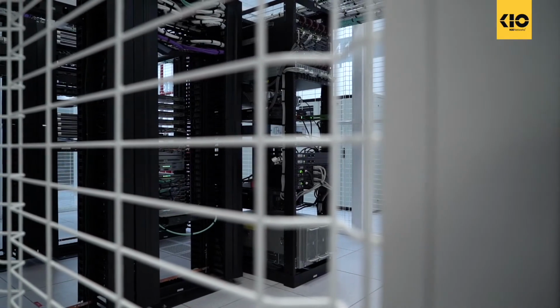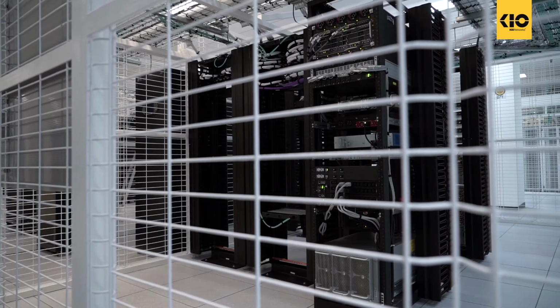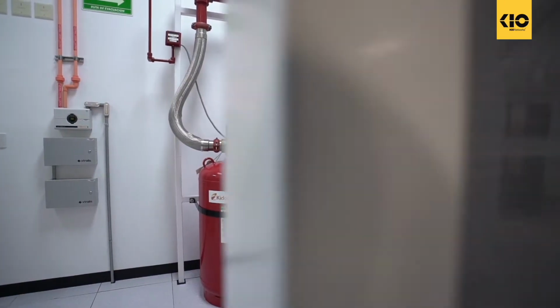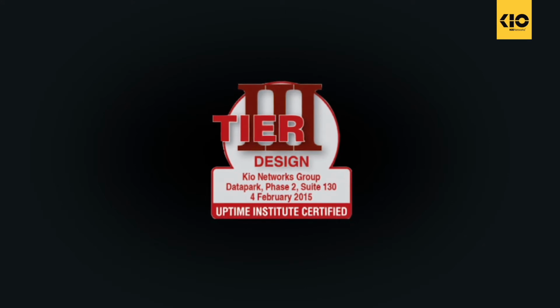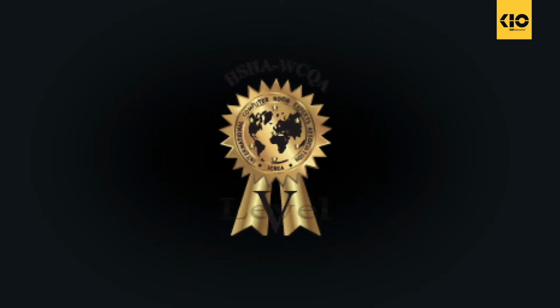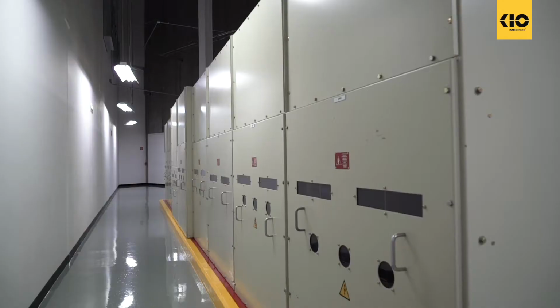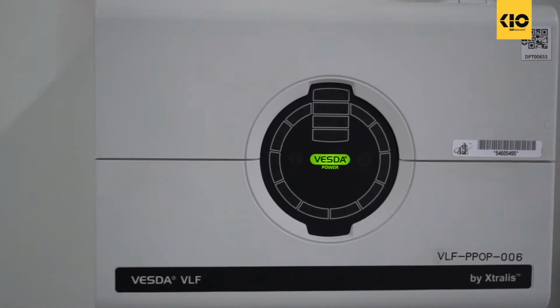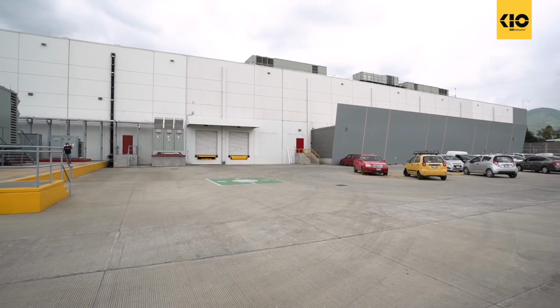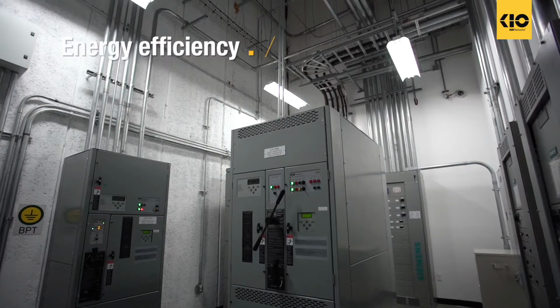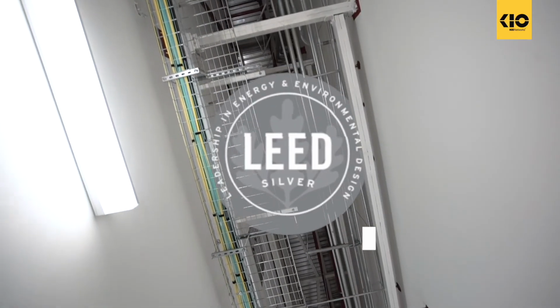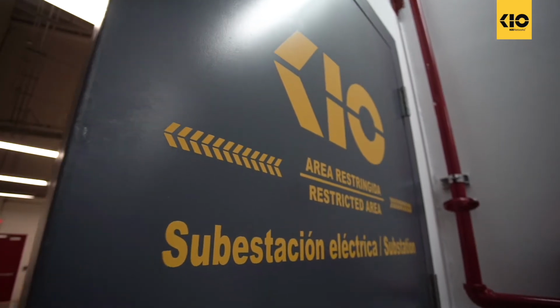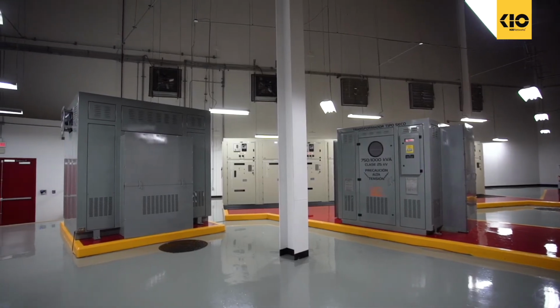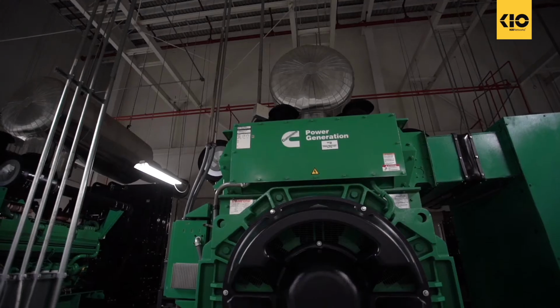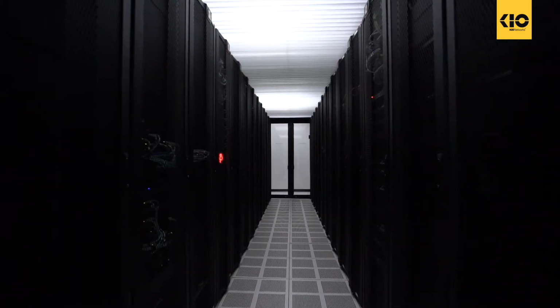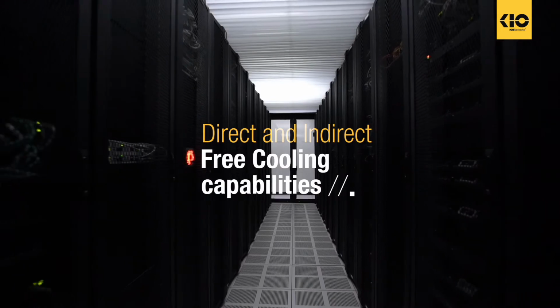This data center has two global certifications associated with reliability and performance standards, such as Uptime Tier 3, which certifies the design and facility, and ICREA Level 5, which certifies the redundancy levels of the electrical, cooling, security, safeguard, and telecommunication systems. It also has certifications for sustainable building and energy efficiency, such as LEED Silver and CETA Gold. Both certifications recognize the crucial characteristics of efficiency in construction and other innovative solutions that allow to reduce energy consumption in the cooling system substantially with direct and indirect free cooling capabilities.